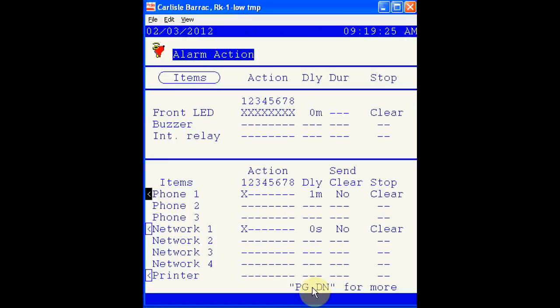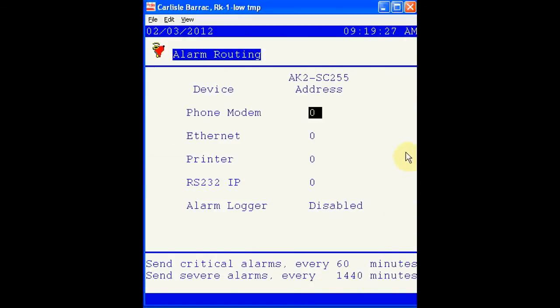Let's page down to verify that the setup is correct. In this case, the 255 is programmed to know that the modem exists on unit 0, the Ethernet is connected to unit 0, and there is no alarm logger installed.